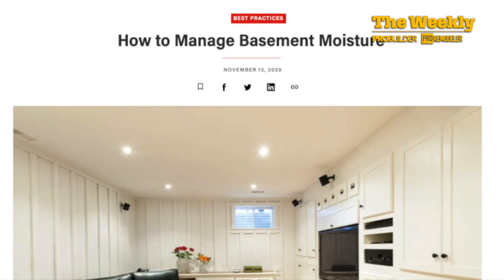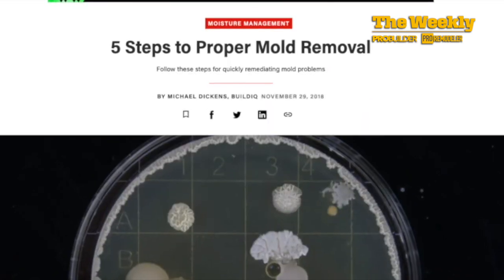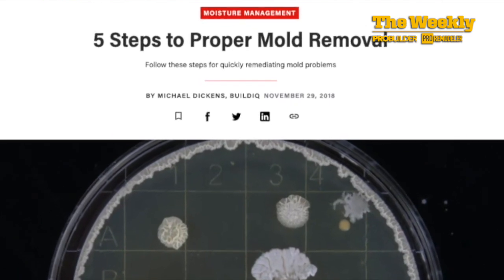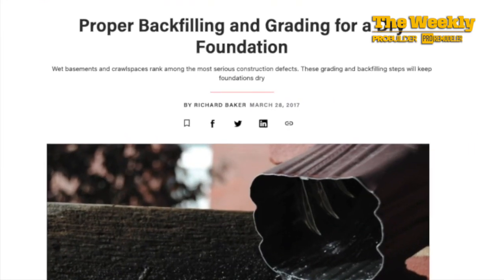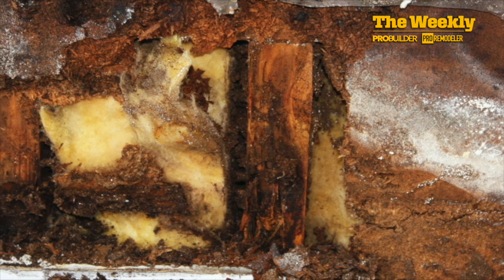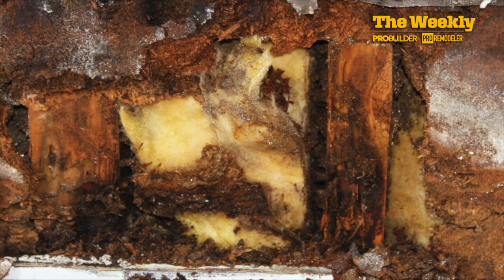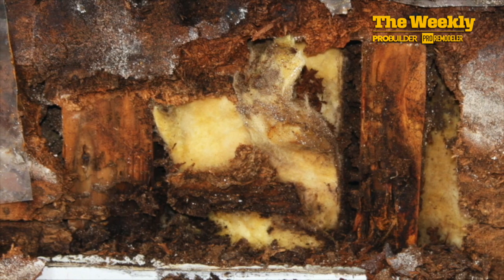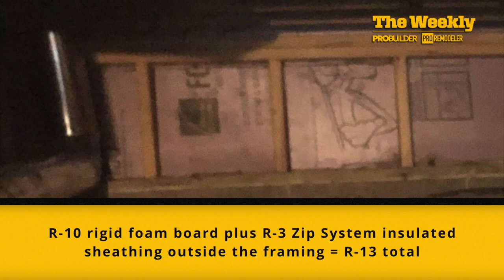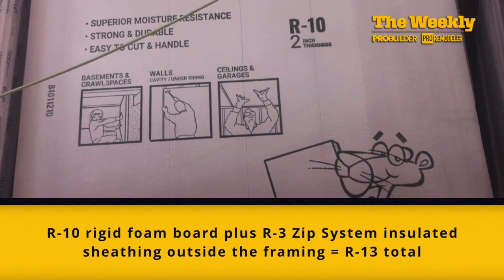Besides, stories about crawlspaces and mold are the most read topics on ProBuilder.com, so I figured my encapsulation journey would make for a good video on the Weekly. Phase 1: remove the existing insulation. Fiberglass — bad insulation in a damp area like the crawlspace — is a no-no. Organic material like kraft paper backing is food for mold. So I removed all the bad insulation and replaced the spaces between the 2x4s and behind the rim board with 2-inch thick R10 rigid foam board.